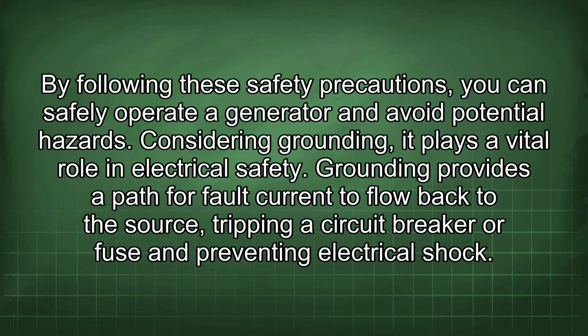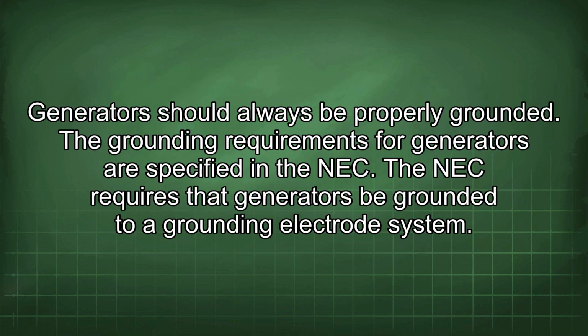Considering grounding, it plays a vital role in electrical safety. Grounding provides a path for fault current to flow back to the source, tripping a circuit breaker or fuse and preventing electrical shock. Generators should always be properly grounded. The grounding requirements for generators are specified in the NEC. The NEC requires that generators be grounded to a grounding electrode system.